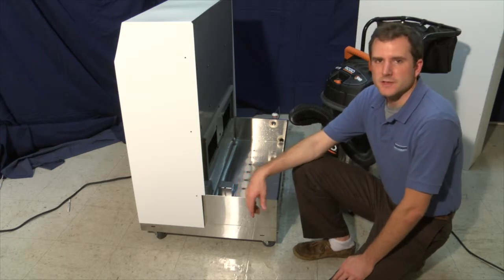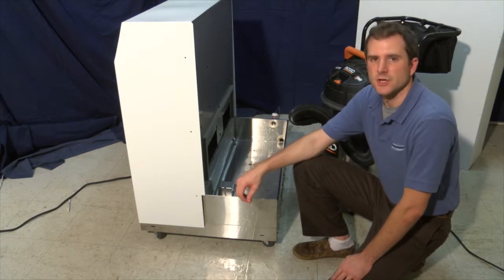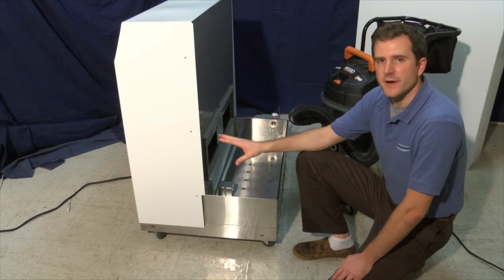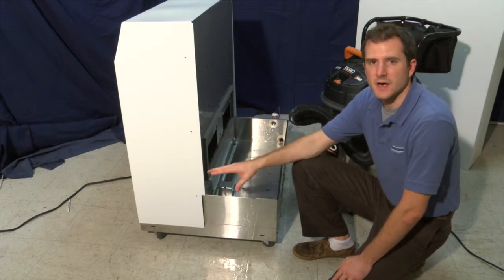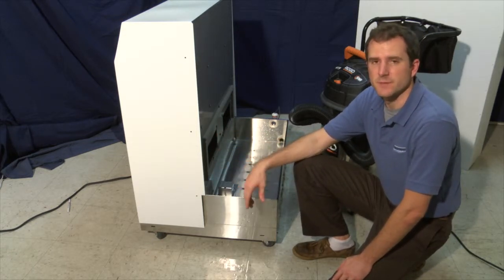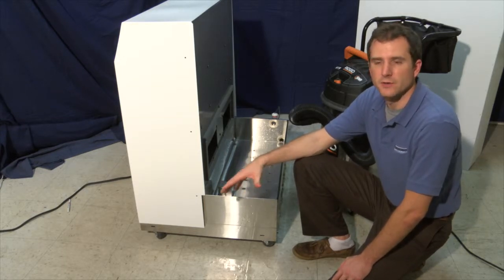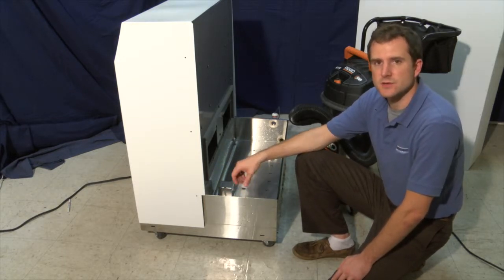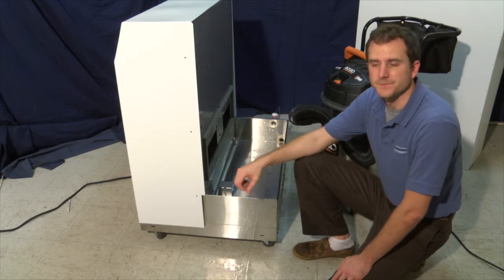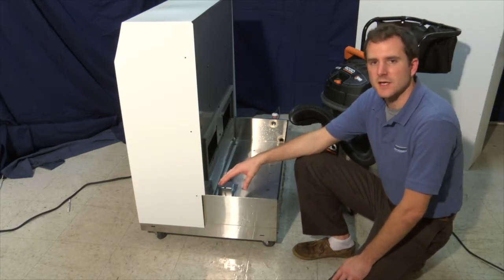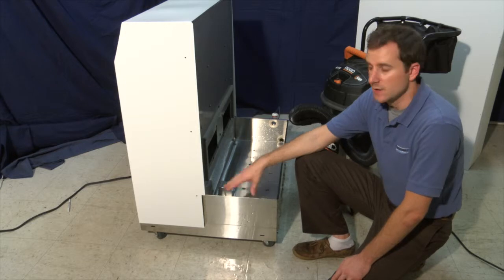The last best practice we want to talk about is seasonal shutdown. A humidifier should never be kept with water inside not being used for an extended amount of time. Stagnant water can create an organic growth or buildup that can damage the transducers or clog the solenoid.